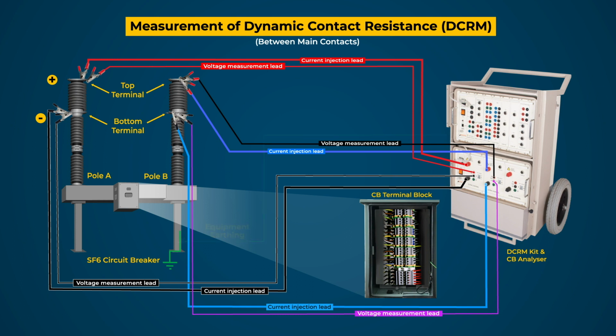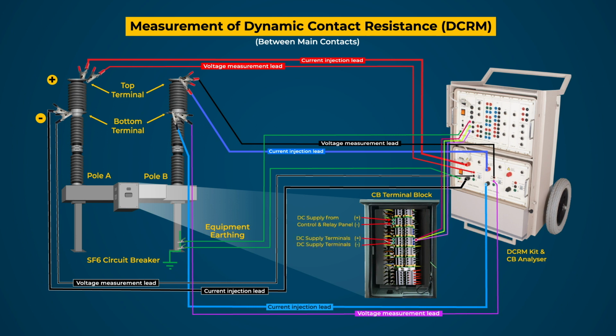Also, connect the master earthing terminal of the DCRM and CB analyzer kit to the equipment earthing. Connect the breaker control leads of the tester to the terminal block of the breaker one by one at the DC point, close coil terminal, and both the trip coil terminals.